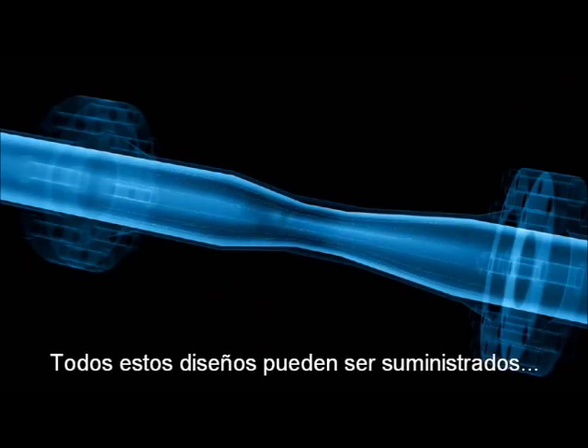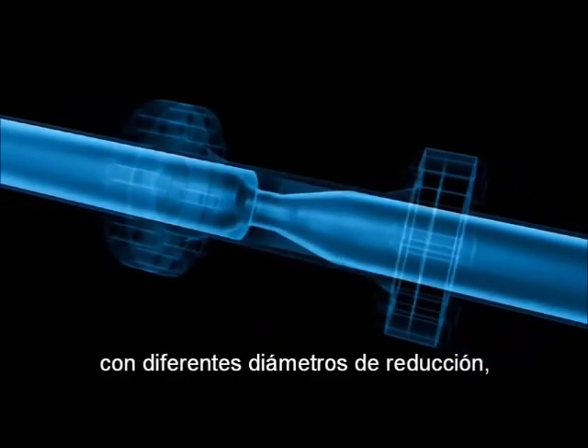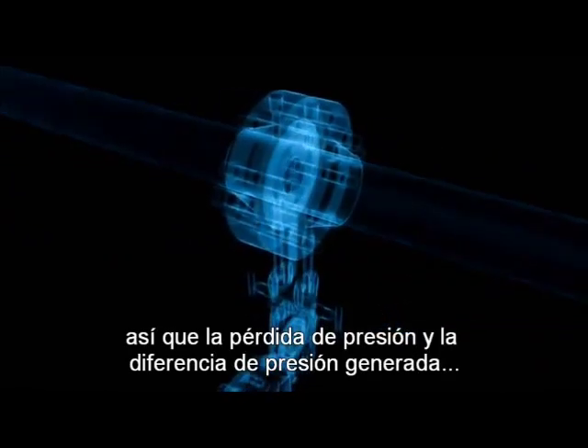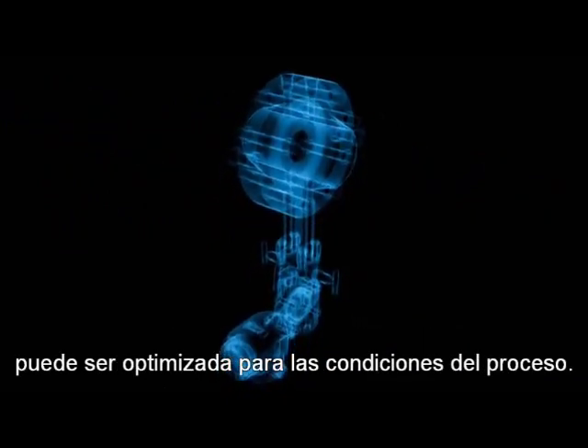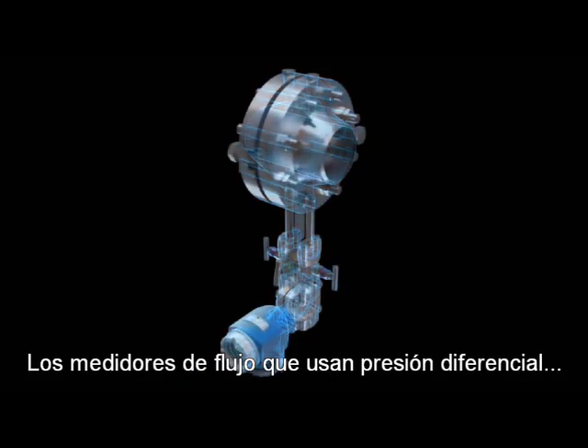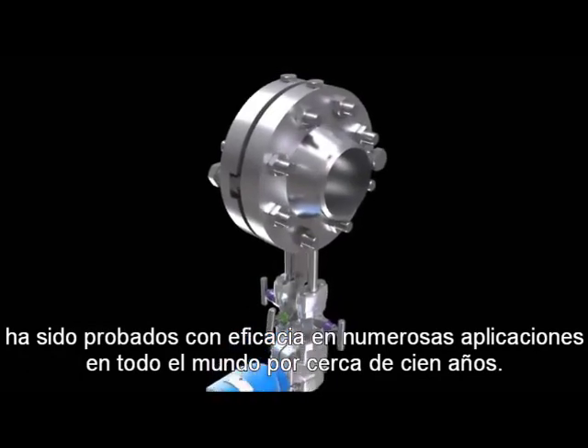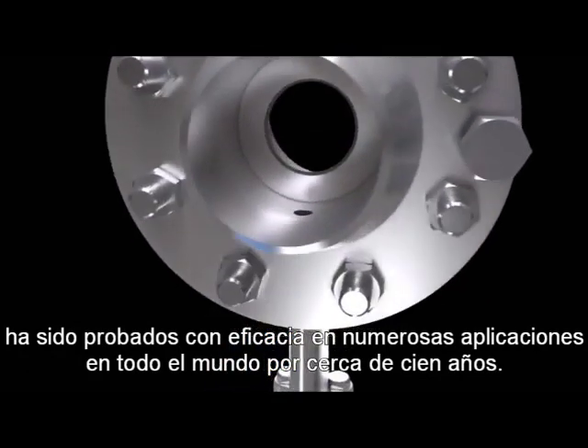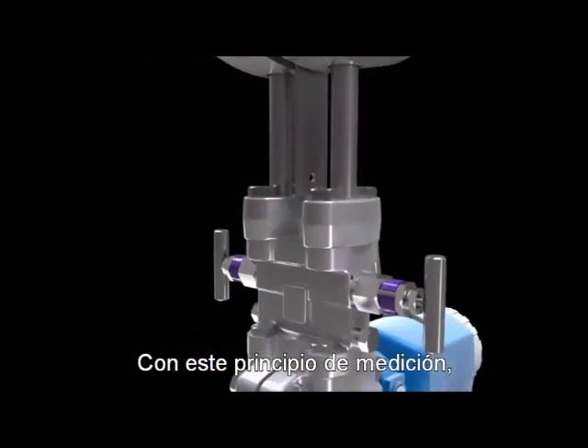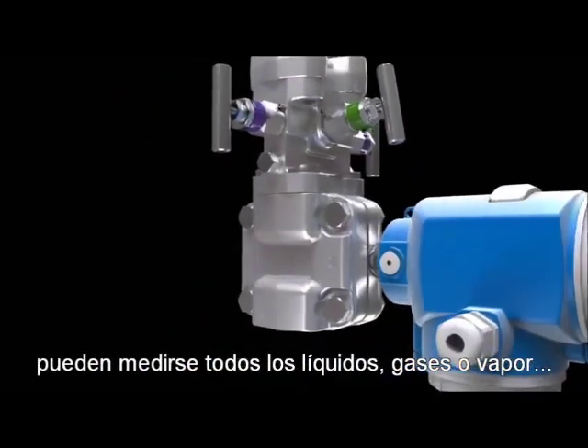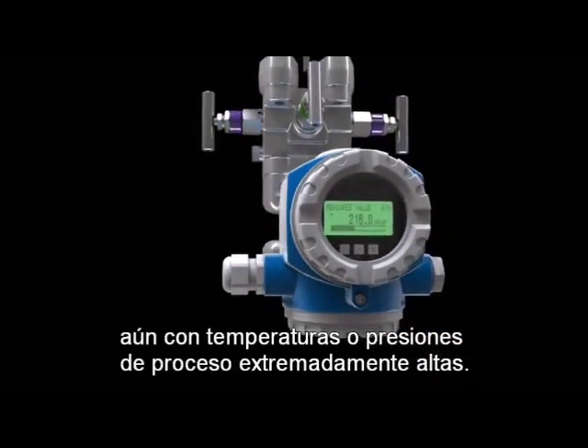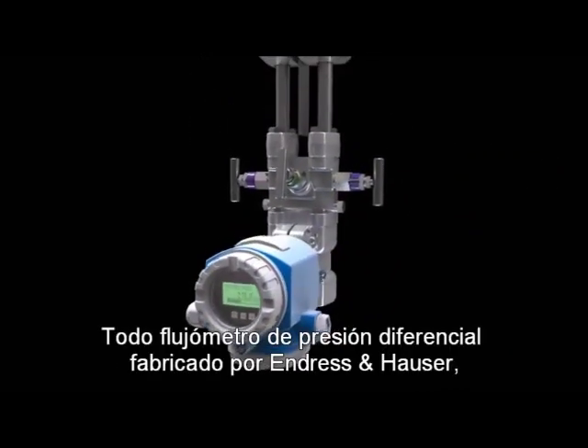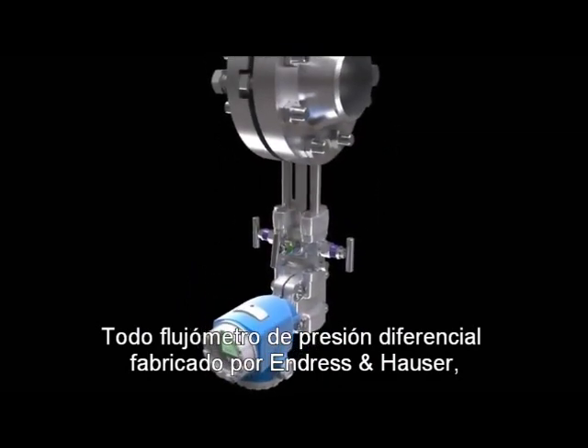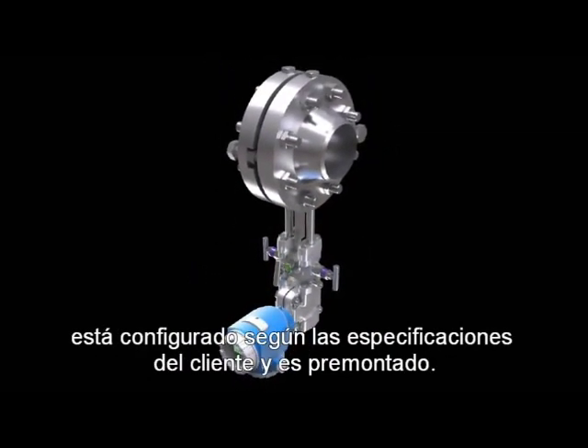All these designs can be supplied with different restriction diameter sizes, so that the pressure loss and the differential pressure generated can be optimized for the process conditions. Industrial flow measurement using differential pressure has been tried and tested in numerous applications worldwide for about 100 years. With this measuring principle, all liquids, gases, or steam can be measured, even at extremely high process pressures and temperatures. Every differential pressure flow meter manufactured by Endress and Hauser is configured to customer specifications and pre-mounted.